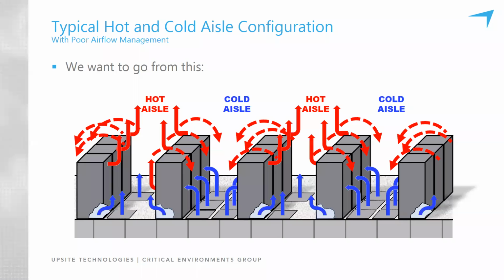So this image shows that even though hot and cold aisle layouts have been implemented in a room, there's the potential for a lot of poor airflow management. You can see that in this image, there's a lot of hot air circulating over the tops of the cabinets. Hot exhaust air can circulate around the ends of the cabinets. As Rob mentioned, aisle end doors are necessary at the row level to prevent that from happening. And conditioned air is being lost out of the cable openings or misplaced perforated tiles. We're going to be covering that in the raised floor presentation. So there's a lot of room for improvement, and row airflow management will help you get to an ideal scenario.